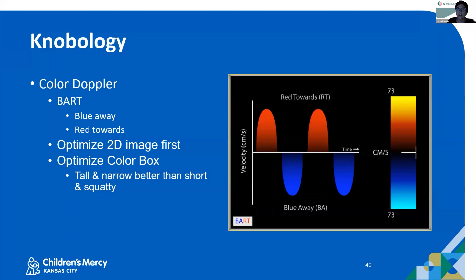So when you hit color, you're going to have so many choices up on your screen. This is another place you can get into the weeds where you start changing too many buttons. So when you're first learning, you want to gain proficiency on the basics, focus on getting the views, and then later when you're good at that, you can explore these more in-depth settings. So the easiest knobs to get familiar with for color, you're going to adjust your scale or your Nyquist limit. You want a lower scale for low velocity flow, higher scale for high velocity flow. You want to adjust your color gain. You can increase it until it speckles and then back off a little bit.